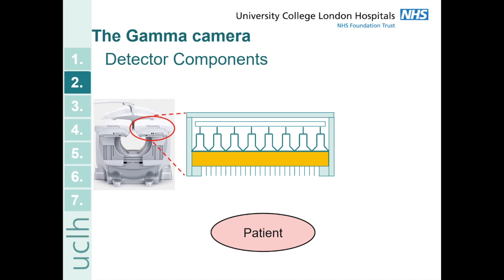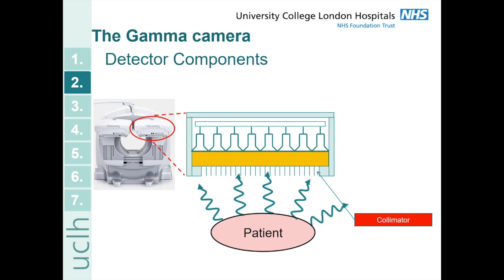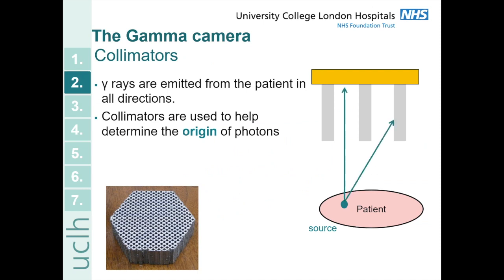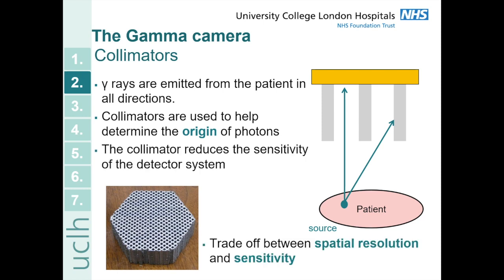In this picture you can see the components of a gamma camera. At the bottom you have your patient who is emitting gamma rays, and each of the gamma rays will first come into contact with the collimator, which is the first part of the gamma camera. They then go into the scintillation crystal, the photomultiplier tubes, and finally the processing electronics to create the image. Gamma rays are emitted in all directions, and the collimators are designed to determine the origin of these photons. A photon coming in straight will go through to the scintillator crystal, whereas a photon at an angle is attenuated by the lead collimator. The collimator reduces sensitivity, so choosing collimators is always a trade-off between spatial resolution and sensitivity.